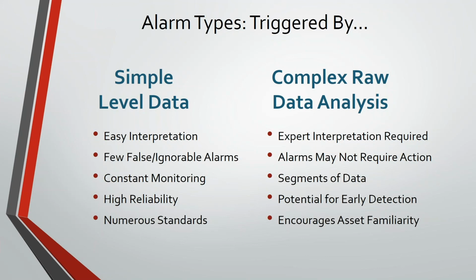But if you, on the other hand, go to a complex version of alarming, switching over here on the right, you might get notified for things where you don't know what it means, right? You might have to do some research, you might have to get an expert involved and make a decision. The next line down here is alarms may not require action. Whereas with simple level data, you have very few false or ignorable alarms, right? You're generally taking action on all the alarms for your simple level data. And so the thing that I like to think of is, do I want to be woken up in the middle of the night by something changing slightly on my FFT analysis? And the answer is, it depends on your asset, right? But probably no, I can look at that in the morning.